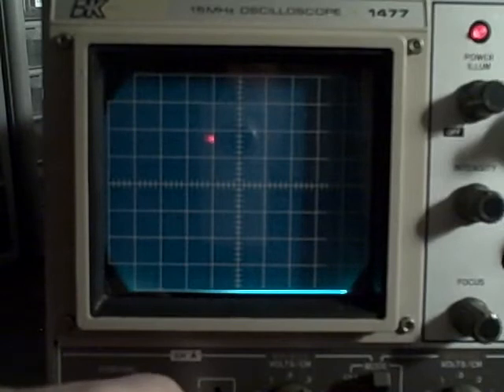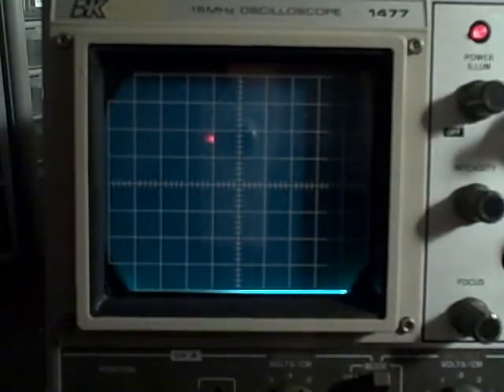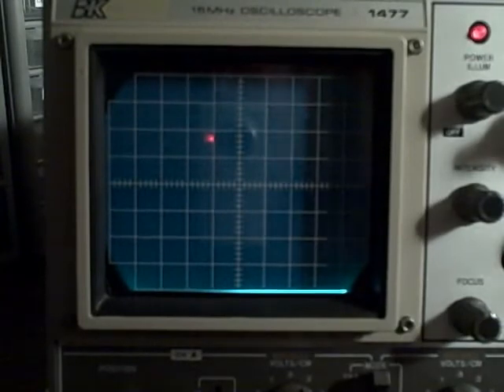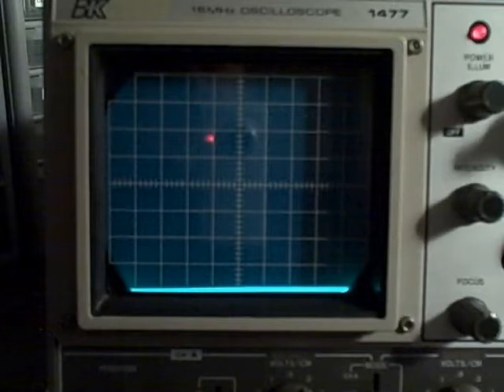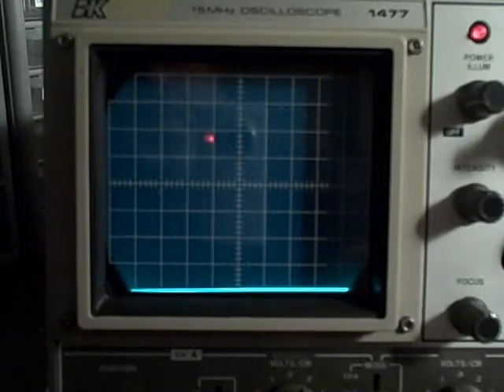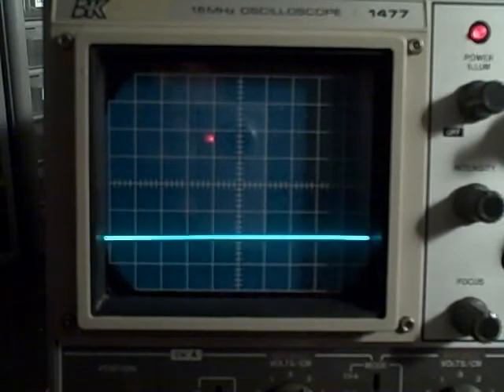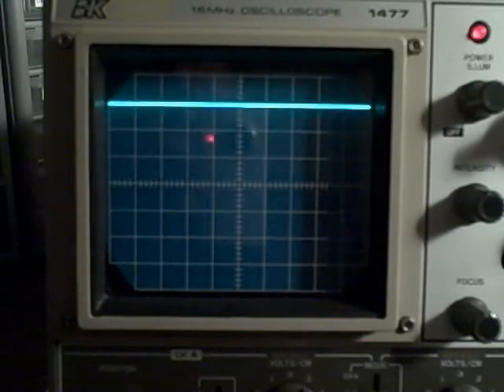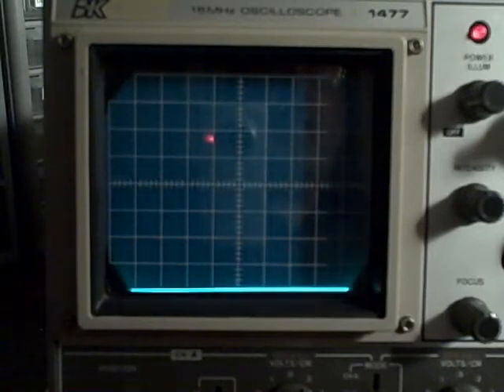All right, we're going to move to channel 2, or B, and we're going to go through the same steps with the calibrator here. Channel B, source on B, and make sure we're at 0. That looks pretty good. We want to be divide by 10, and we are in the lowest range, 0.01, so we're going to go up 1 step at a time. 1, it's 0.01, 0.02, 3, 4, 5, 6, 7, 0.08. Perfect.